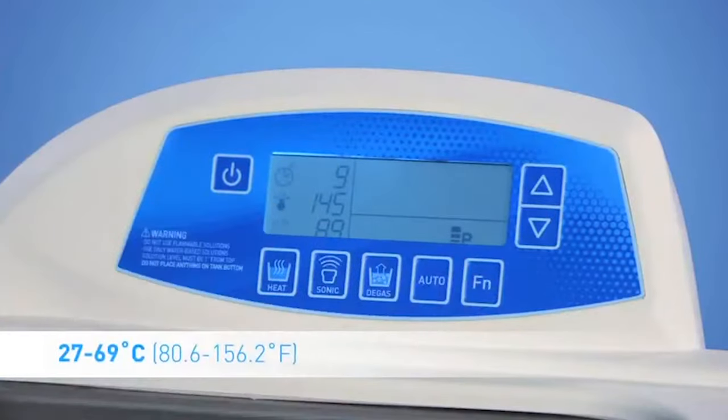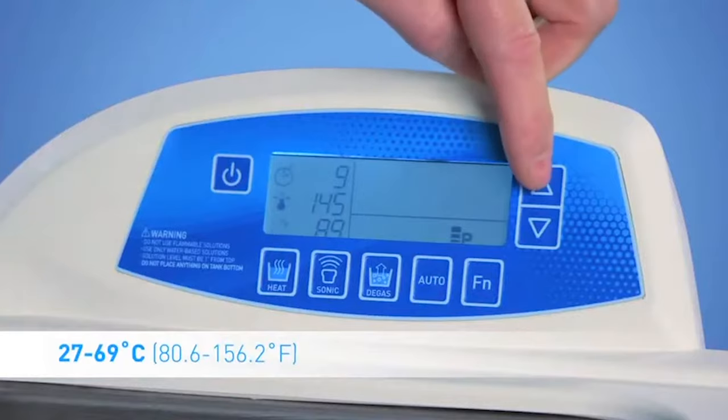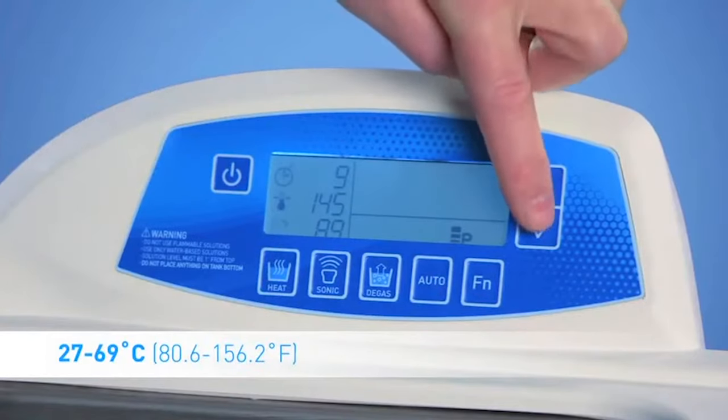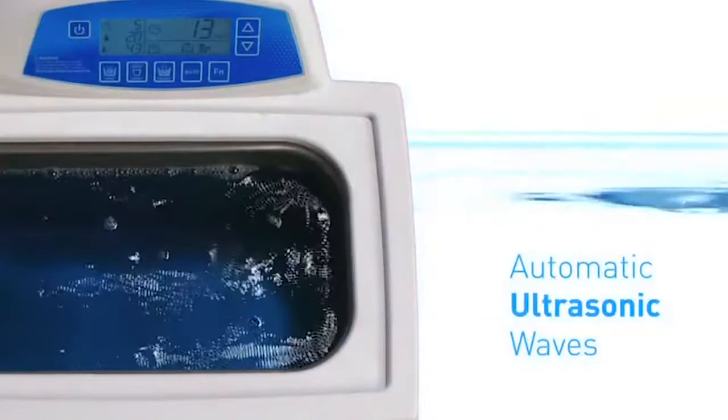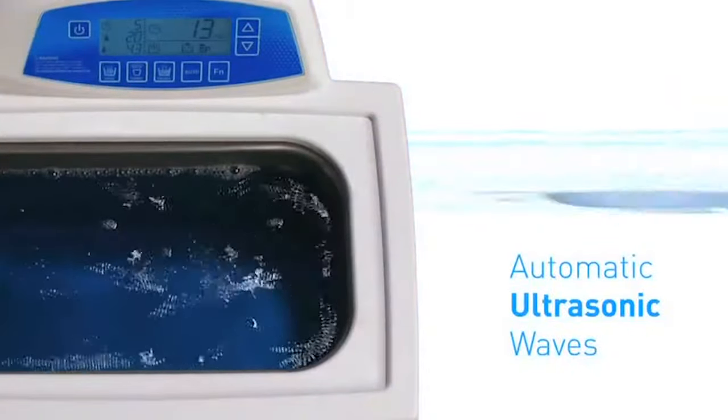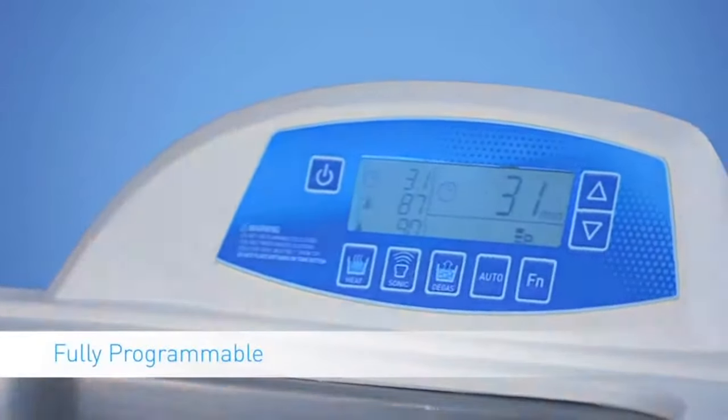You can set temperatures from 27 to 69 degrees Celsius or 80.6 to 156.2 degrees Fahrenheit. Once the program temperature is reached, the ultrasonic waves are automatically activated.